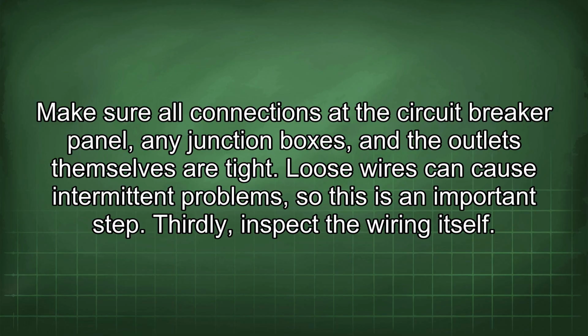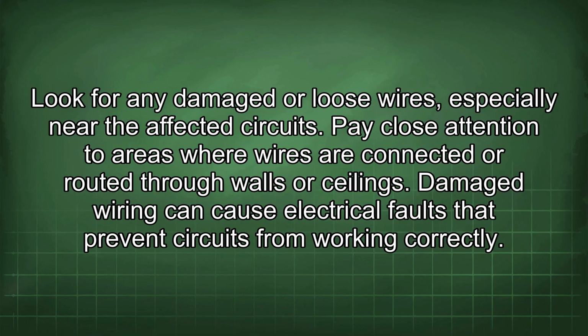Thirdly, inspect the wiring itself. Look for any damaged or loose wires, especially near the affected circuits. Pay close attention to areas where wires are connected or routed through walls or ceilings. Damaged wiring can cause electrical faults that prevent circuits from working correctly.